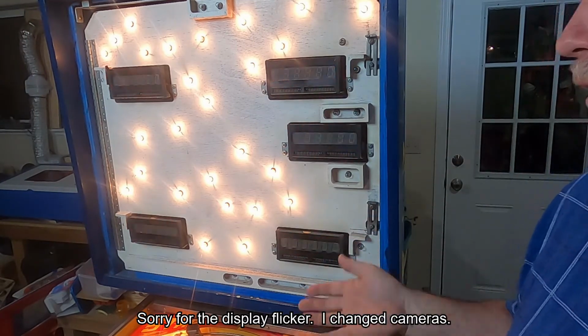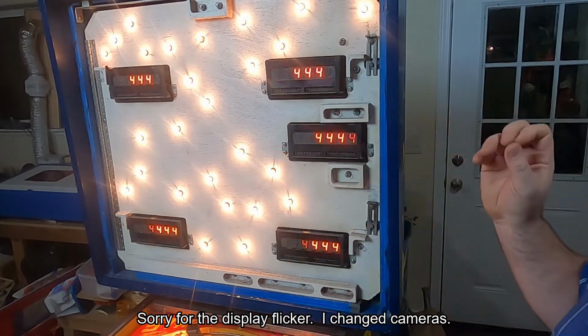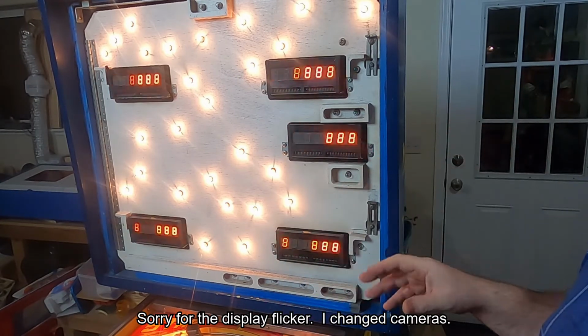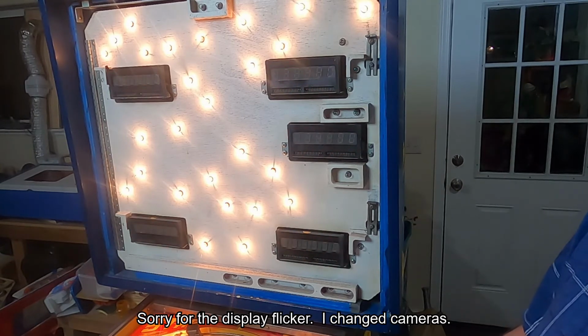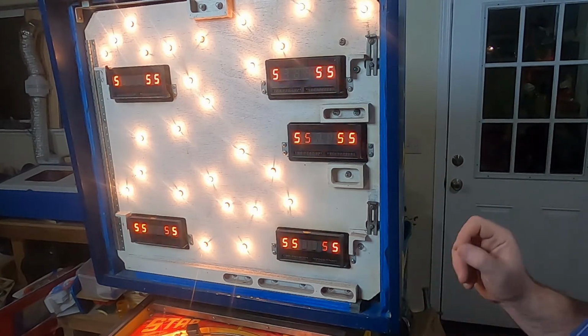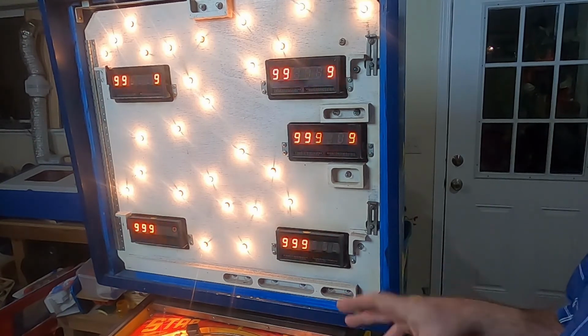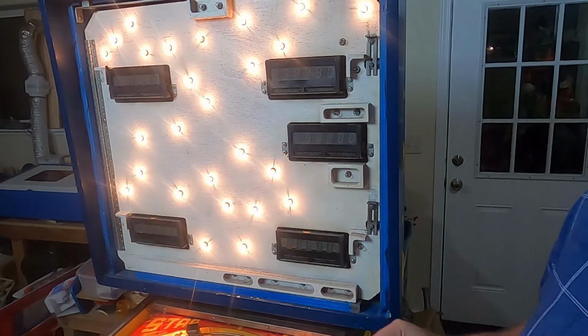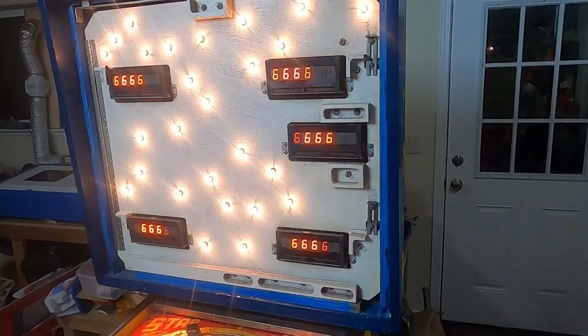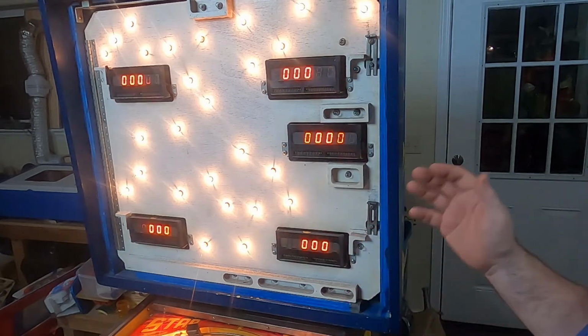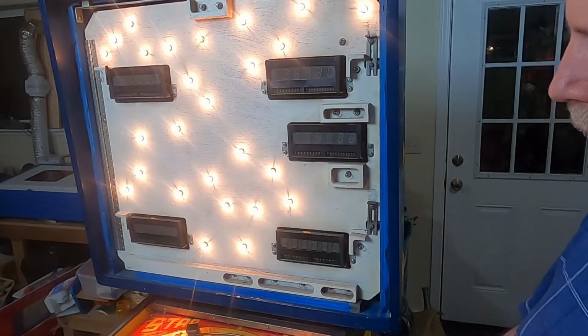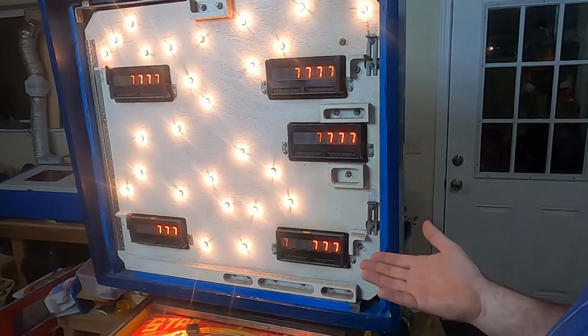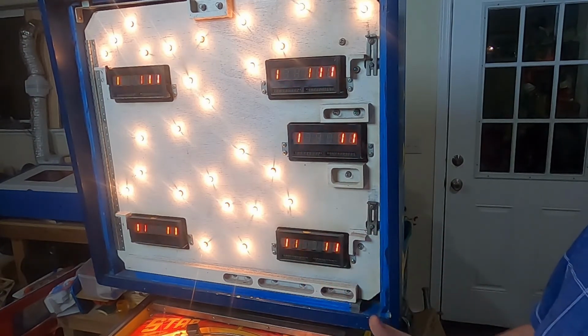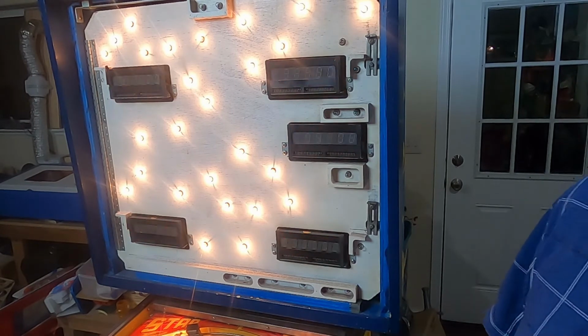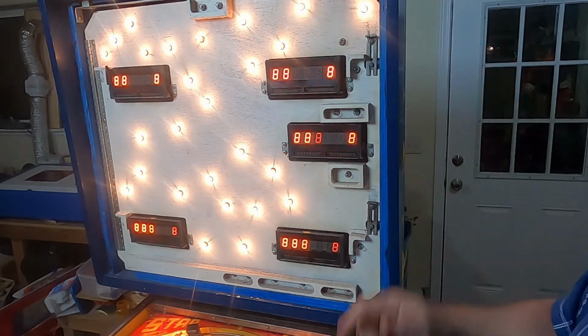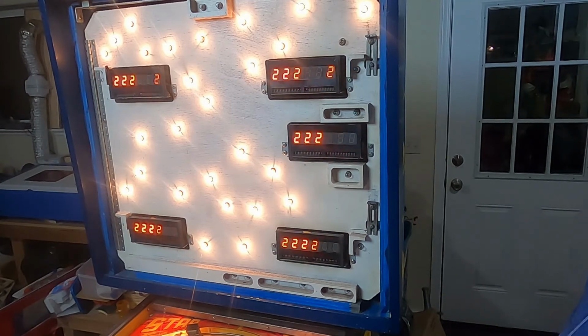Lessons learned in the process of doing this: double check, double check, double check. Don't just visually inspect. Check with a volt meter or an ohm meter. Make sure that there are no shorts between your high voltage and your grounds, basically make sure you don't have any shorts between any pins that shouldn't be connected. I knew this, I did this on several of them, I didn't do this on the last one. Again, blew a fuse. Not that a fuse is the end of the world, it did what it's supposed to, protect the system, but it could be a lot worse if that fuse doesn't fail, if somebody doesn't notice, gets a new machine, and somebody has modified that fuse and put in a higher amperage fuse than should be there.